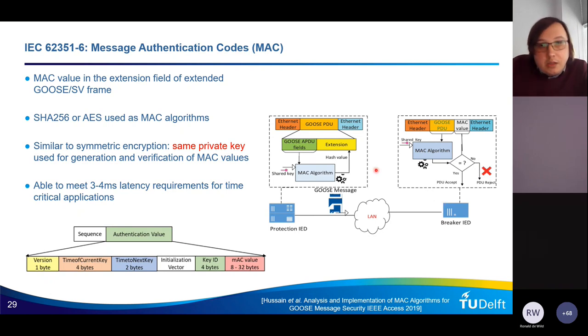So how it works is that we take the GOOSE message and use the MAC algorithm to generate the message authentication code. So we generate a hash value. This is just like a light signature. And then we send the GOOSE packet together with this signature to the breaker IED. The breaker IED will take the GOOSE packet.